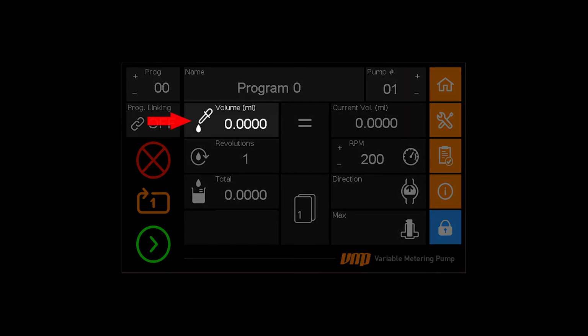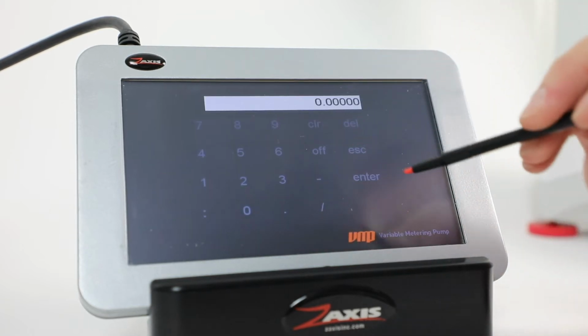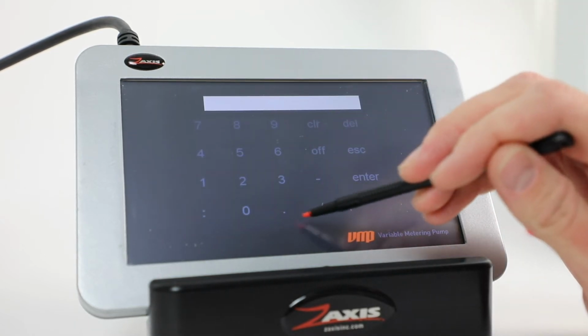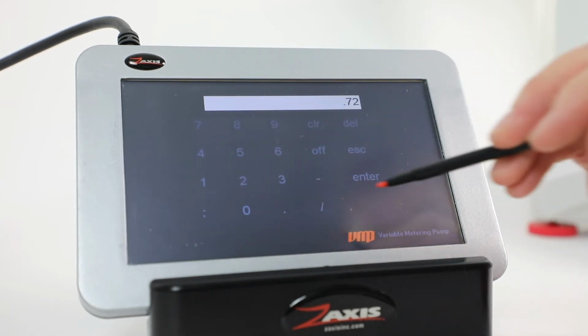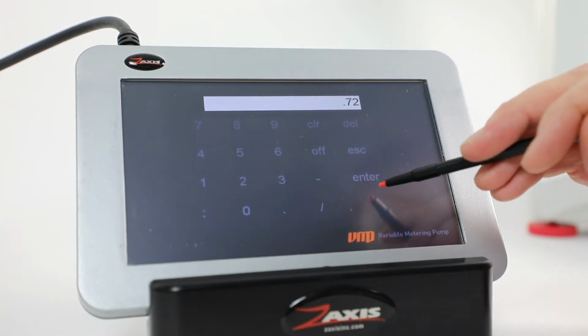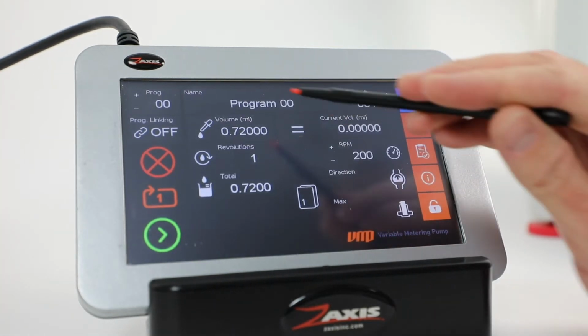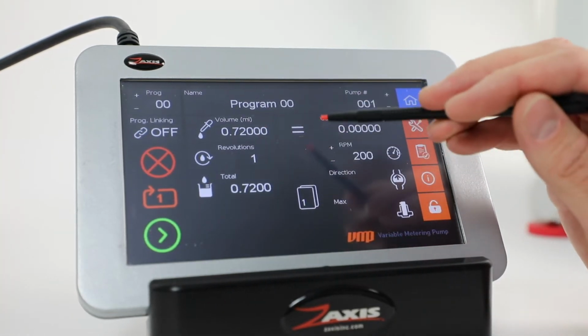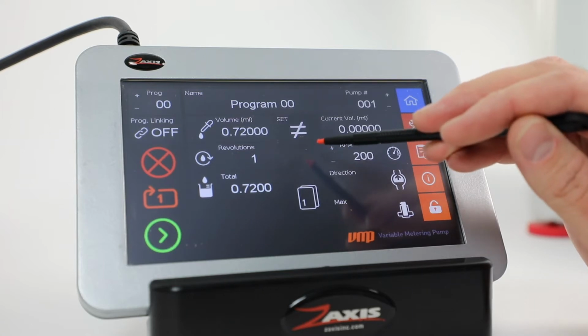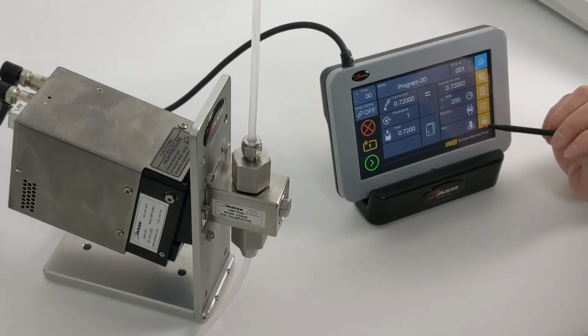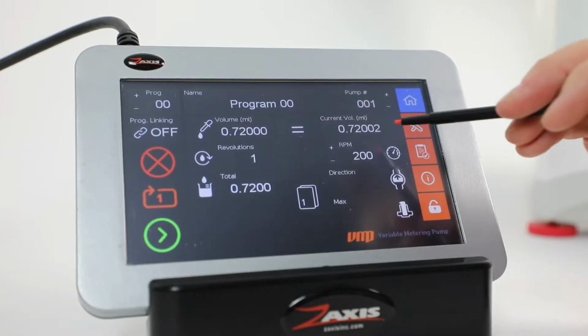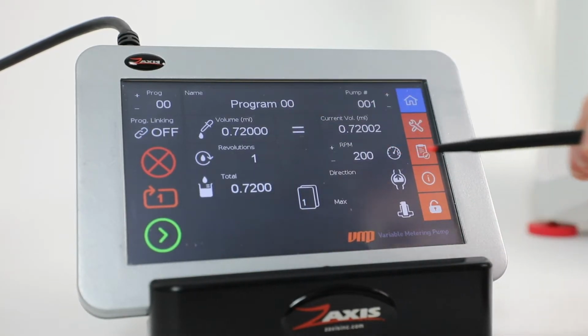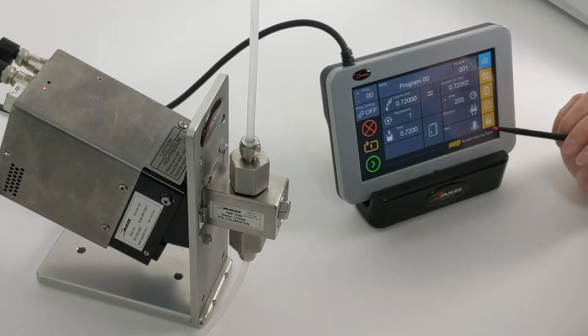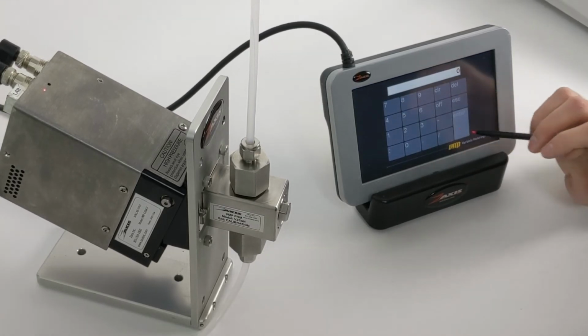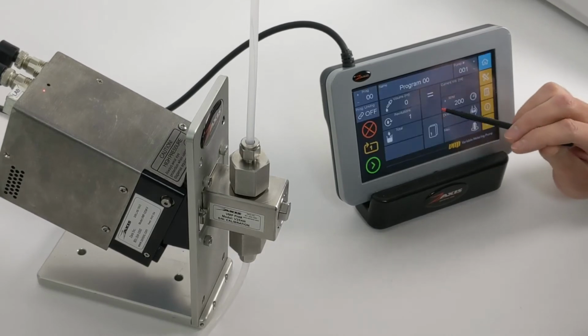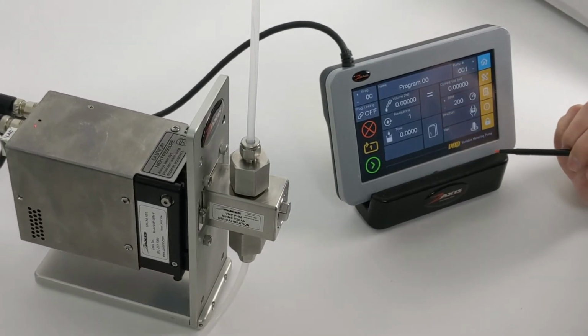To change the volume, just press the volume button and you can enter in whatever volume you want. This is a 3/8 pump head, so its max is going to be 0.72 milliliters. And then once you set a volume over here, the equal sign in the middle will flash, indicating that you need to set it. So we'll hit set, and the pump will adjust. And as you see, the current volume is changed to the volume you put in over here. So if you want to change it back to 0, just click volume again and set to 0. And then the set button flashes again. We'll click that, and it went back to 0.